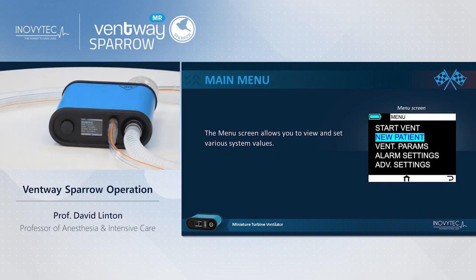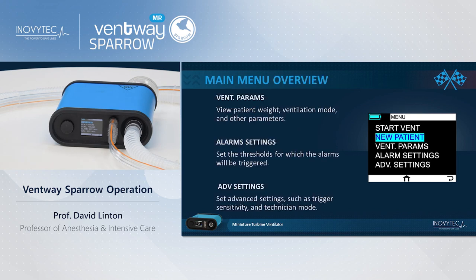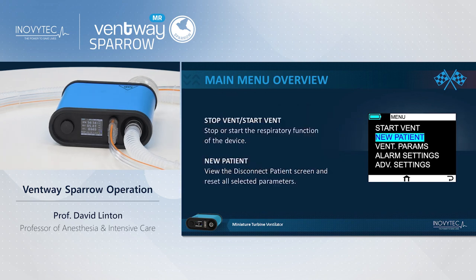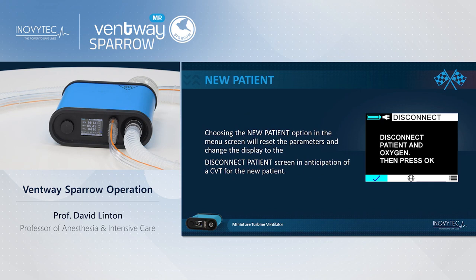When you move the cursor to main menu and select the main menu, you have the option to start or stop the ventilator, to enter a new patient, to change the ventilator parameters, to set the alarm settings, and then there are some advanced settings. Remember that if you push new patient, you will stop or start the ventilator. It will give you the option to confirm it, because it's a dangerous selection. You'll have to confirm it twice, and the ventilator will stop for the new patient or reset.